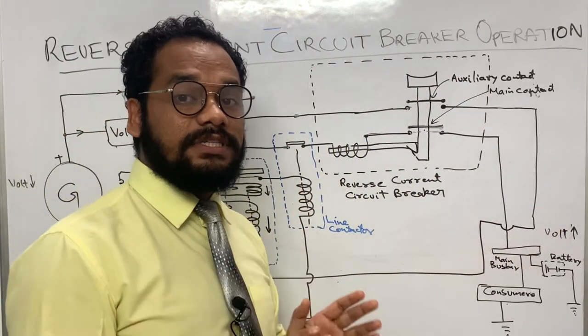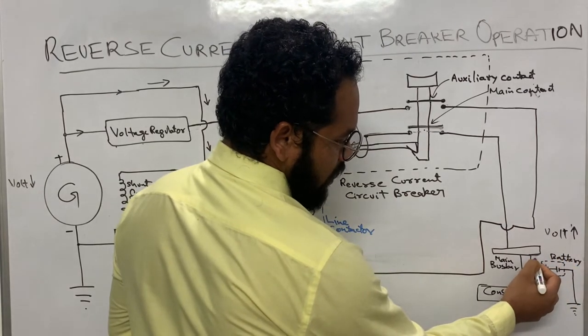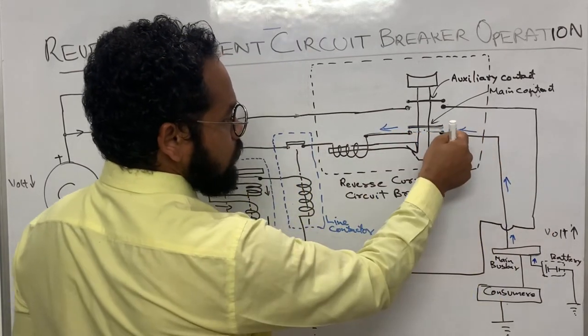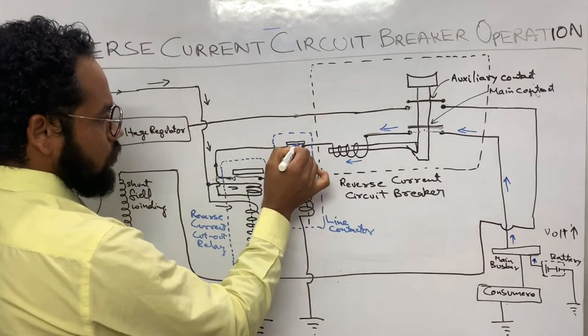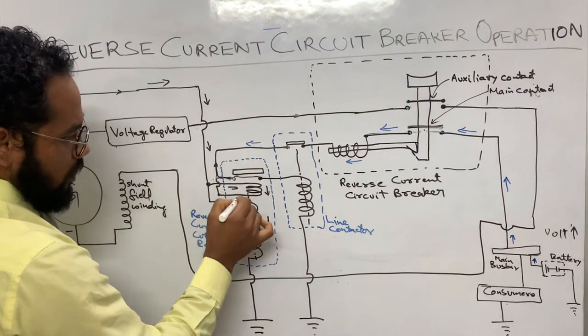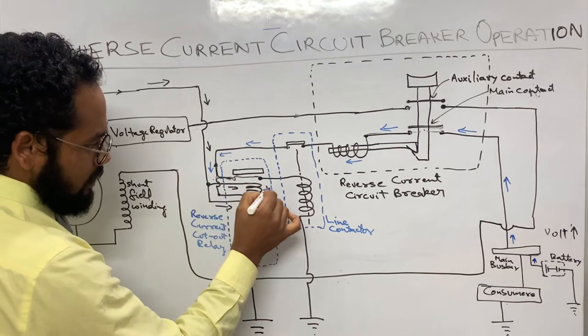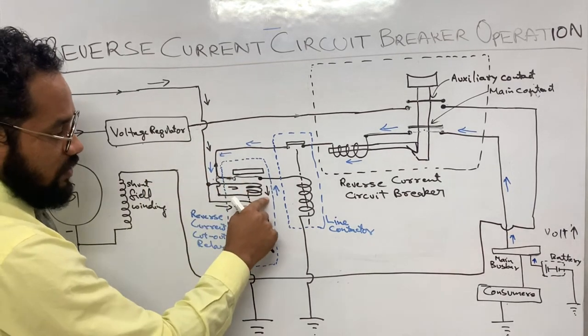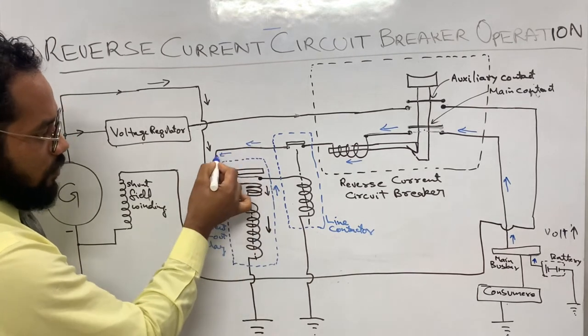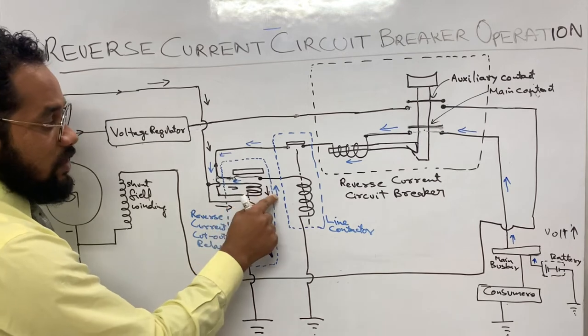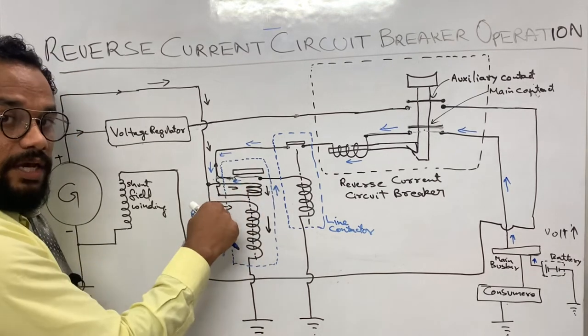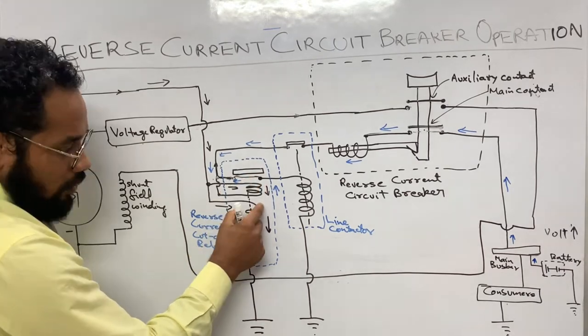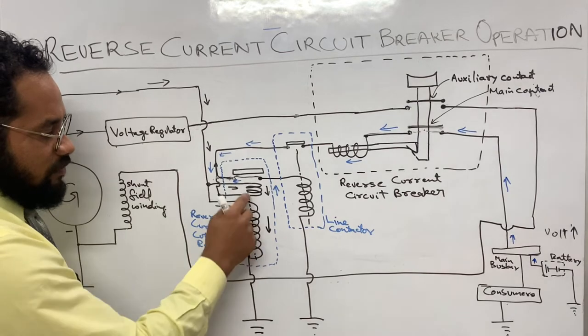The current flowing from the battery end towards the generator is called reverse current. It goes through the main contact, through the coil, through the line contactor contact to the current coil — and the reverse current flows in the opposite direction through the current coil. Since it is energized in the opposite direction, the magnetic effect of the current coil will not assist the magnetic effect of the voltage coil. Both magnetic effects are opposing, so the core gets demagnetized or neutralized.